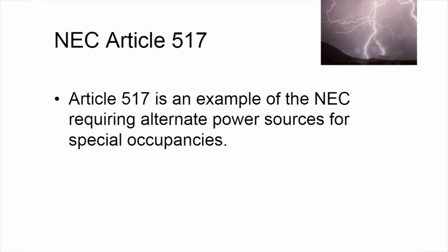The other unique thing about Article 517 is it allows us some level of flexibility in how we configure the systems. We'll provide some examples of that later in the presentation. And also, unlike other areas of the code, Article 517 allows the engineer some latitude in sizing the EPSS, including the use of historical data and prudent demand factors. So we no longer have to size the unit purely based on connected load.